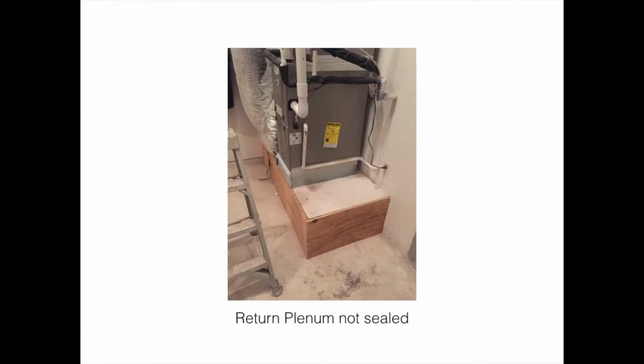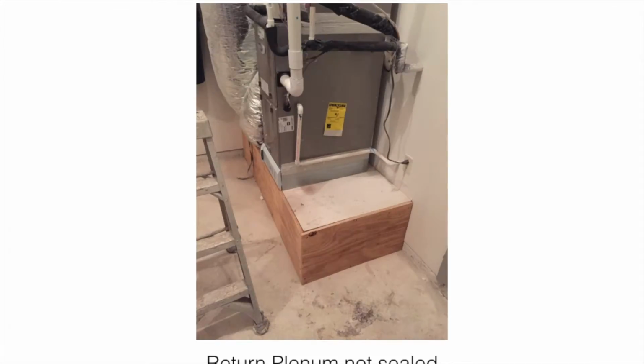This is a picture of return side duct leakage. They basically put these plywood boards up around the bottom of the unit without sealing any of the seams. This means that air is going to be drawn in from this space. If this were a garage space, there would be air quality issues. This is most likely unconditioned air that is now going to make its way into the system.